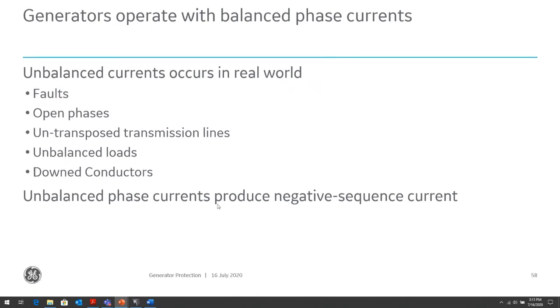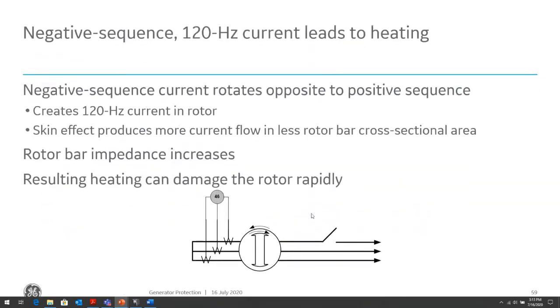So how do we protect against this? Fairly simple. We have a negative sequence or an unbalanced relay, which is looking at the 3 phase currents and seeing what kind of unbalance we have across the 3 phases. And then we will trip appropriately depending on the amount of imbalance. And this again might be coordinated for external fault conditions, because again, if the system is solidly connected, it's not going through a GSU, a ground fault out in your system will cause an unbalance. So you want to coordinate with those situations.